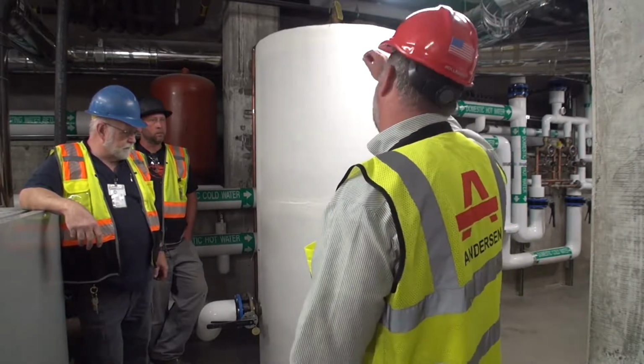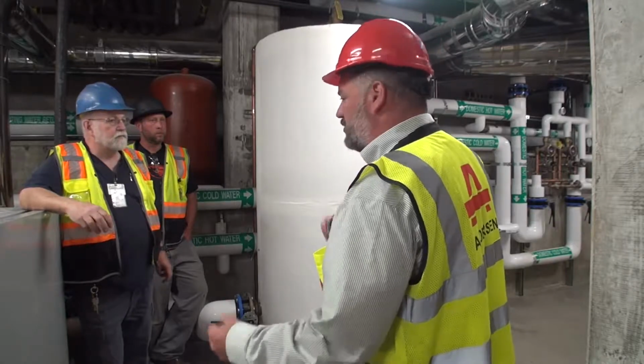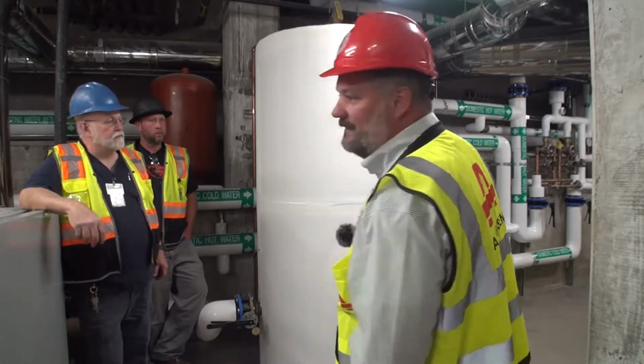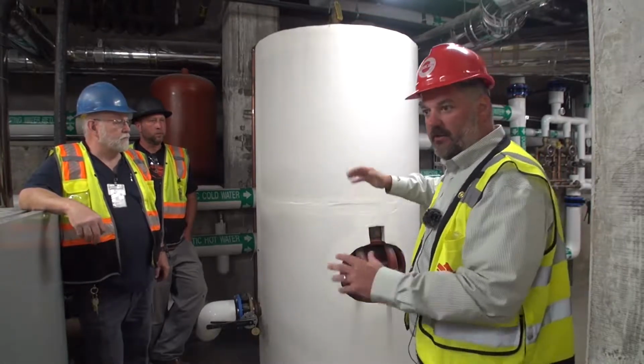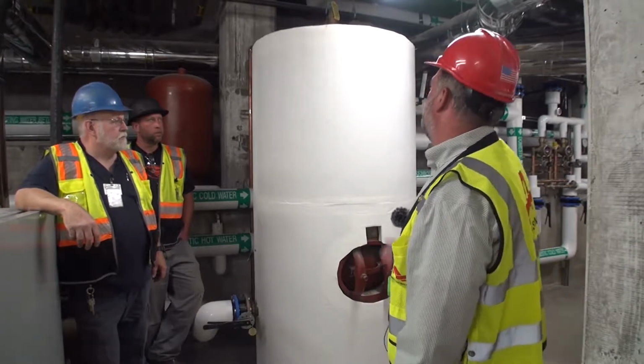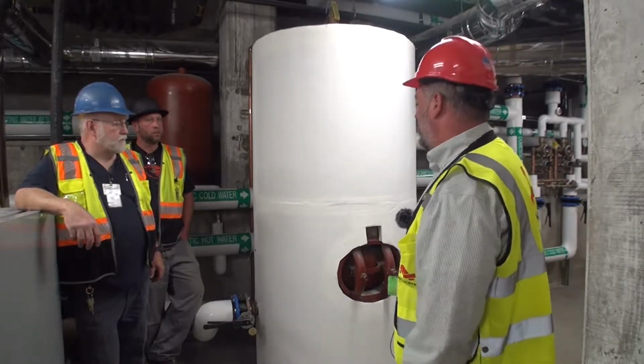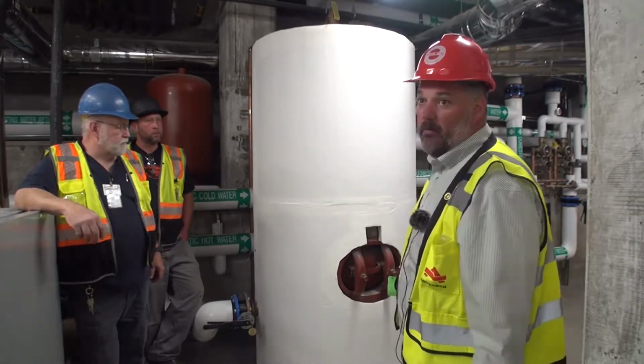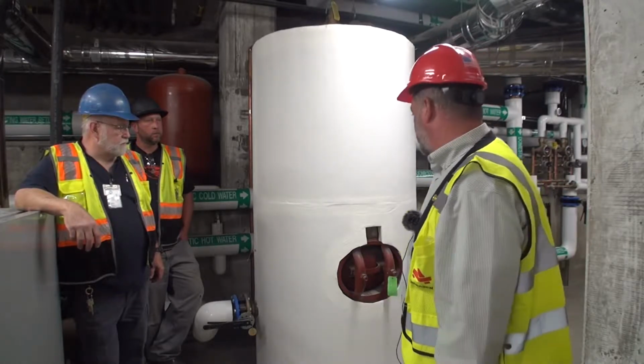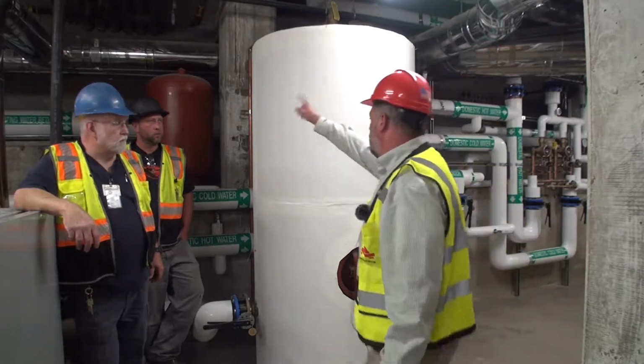If we have a little bit of spurting, but the water's not scalding hot, more than likely that's a pressure issue that we've got to figure out what's going on there. But typically with those relief valves, you'll never see them operate, which is a good thing. That's a safety right back here.